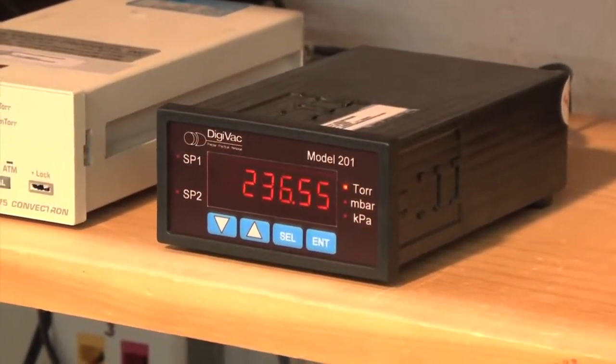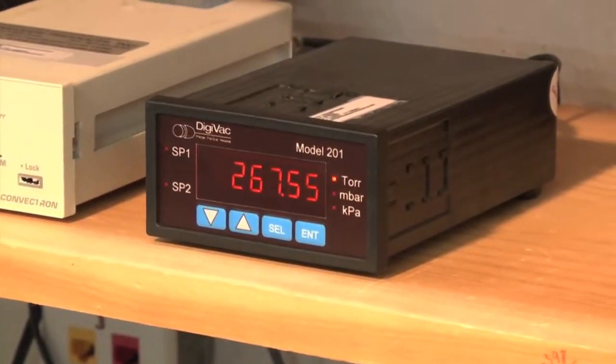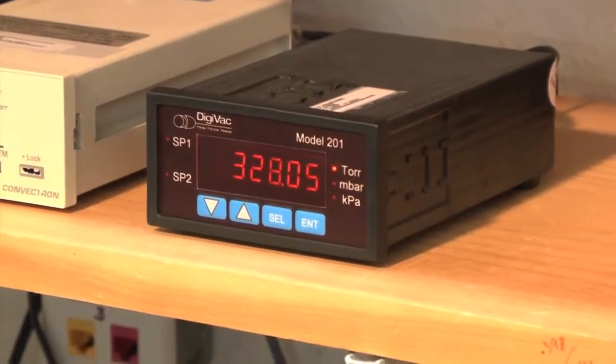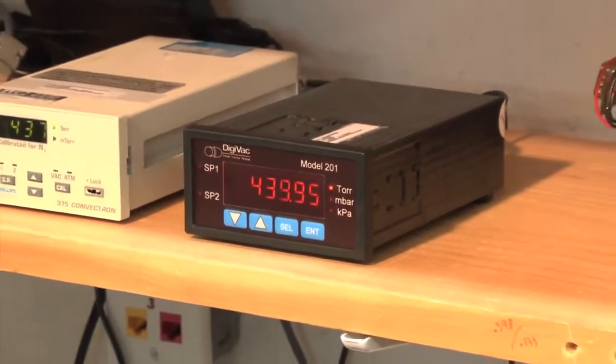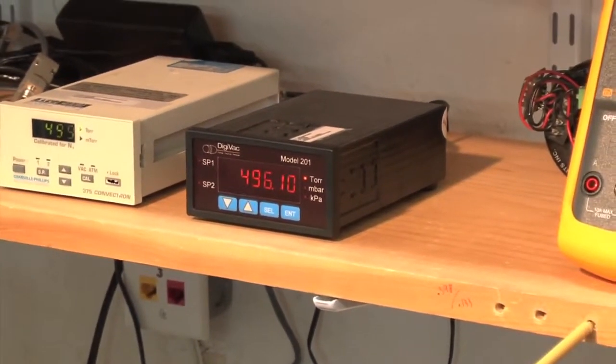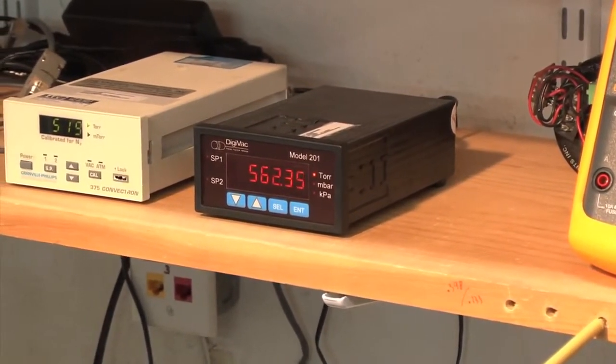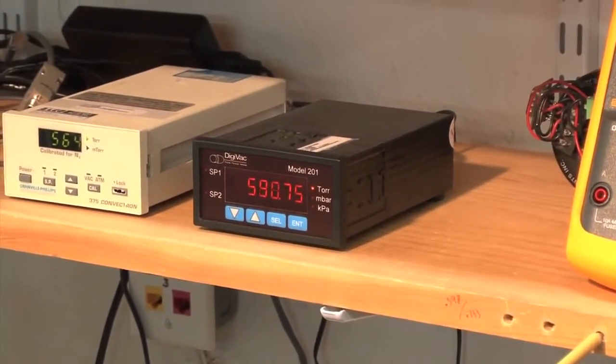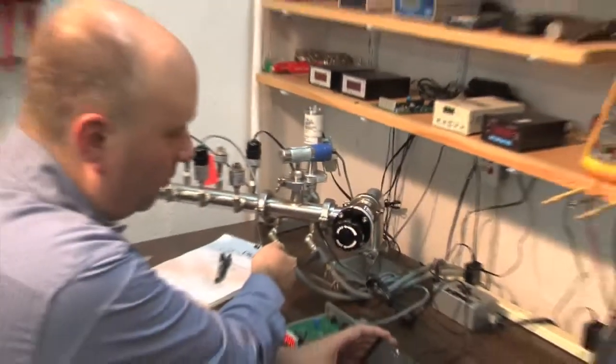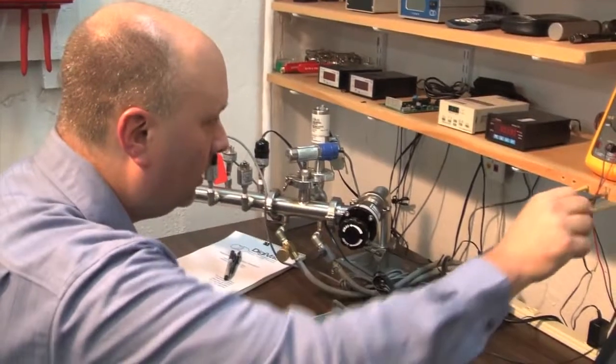Now we can calibrate our 801W at any pressure higher than 500 torr. We certainly do not want to calibrate at atmosphere because atmospheric number changes on any given day. For good practice, we like to use 600. We'll approach that. 603 torr, acceptable place to take a reading.